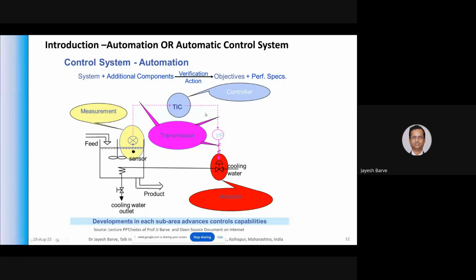So data goes in, some number crunching is done, and then some action is to be taken. The action is transferred by the decision-making block to the actuator. The actuator will decide what to do to maintain temperature - whether to increase or decrease the cooling water flow - so that temperature can be maintained within the performance specs.